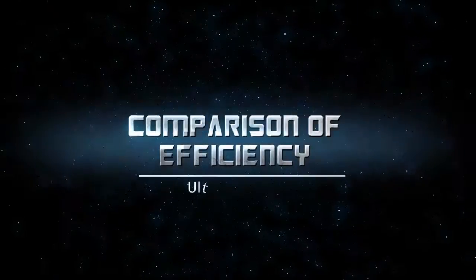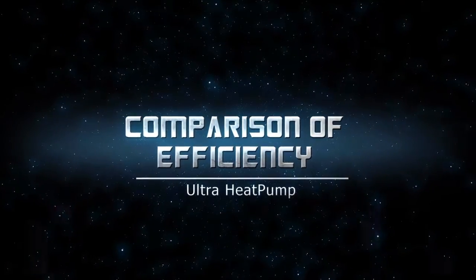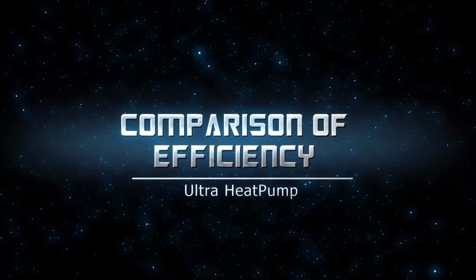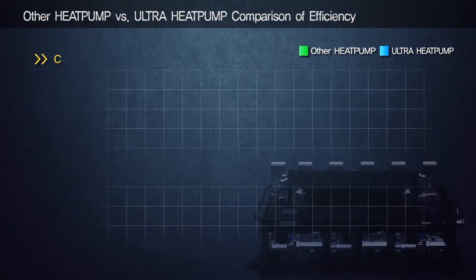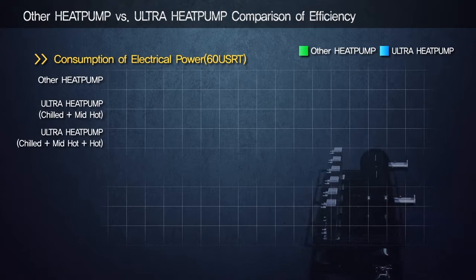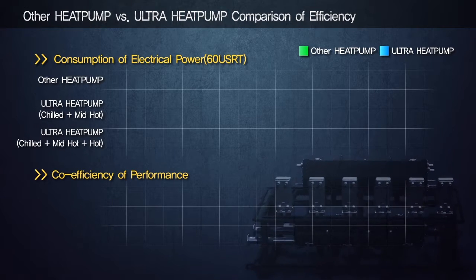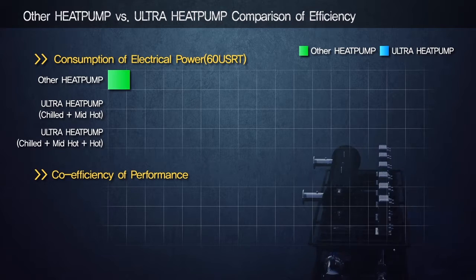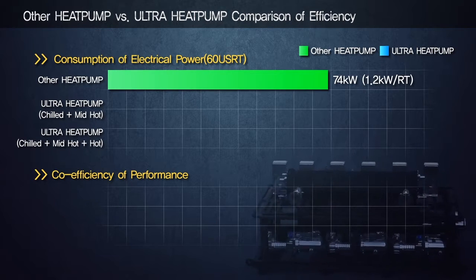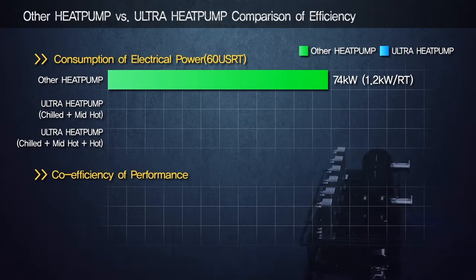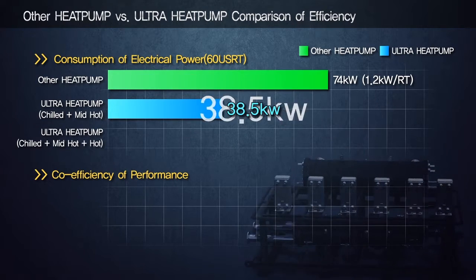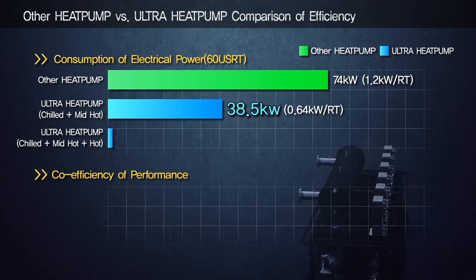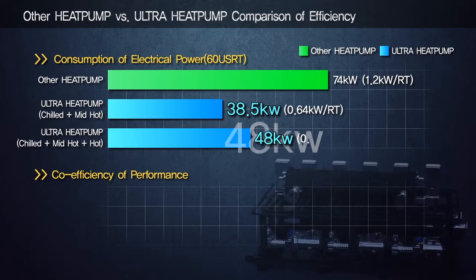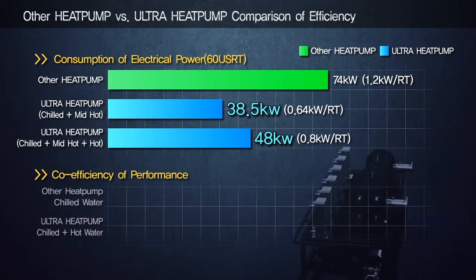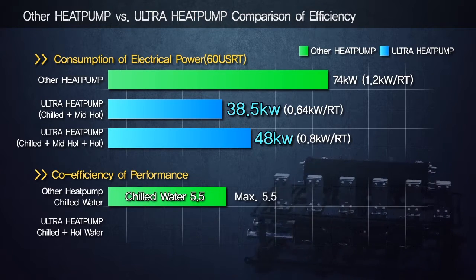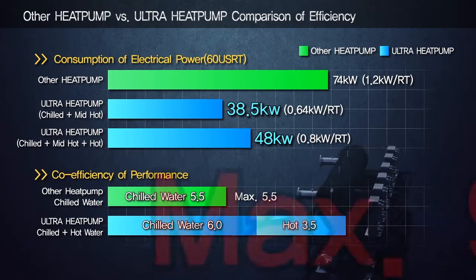In terms of performance, the ultra heat pump disallows other competitors' challenge. The representative difference is consumption of electrical power and efficiency, which is COP. Consumption of electrical power of an existing heat pump is 74 kilowatts, while the ultra heat pump shows 38.5 kilowatts and 48 kilowatts for simultaneous use of chilled and hot water and separate use respectively. Maximum COP of the ultra heat pump is 9.5, while others show 5.5.